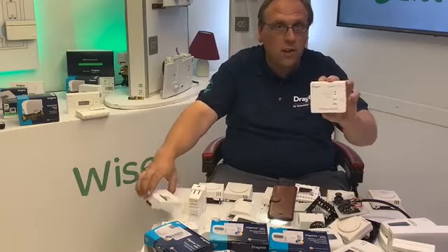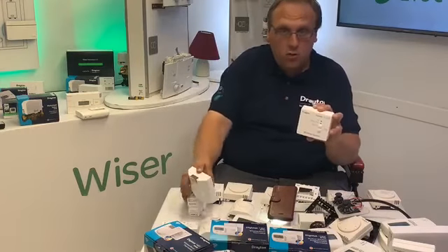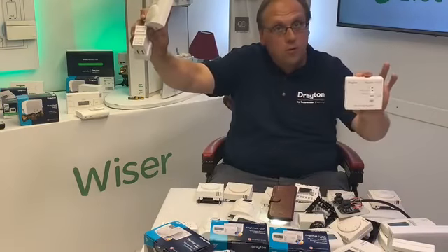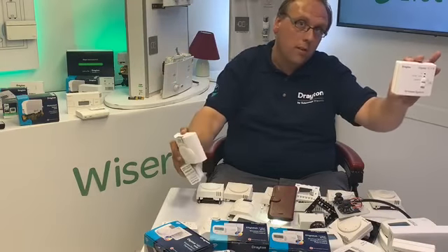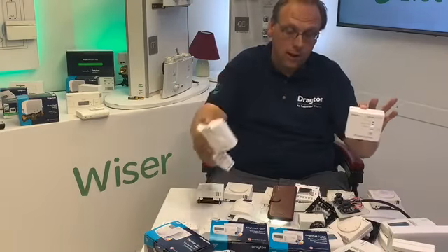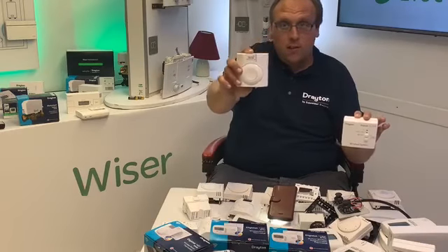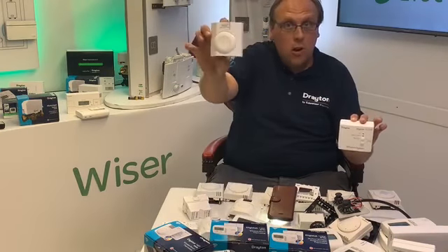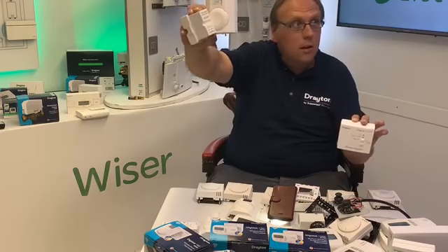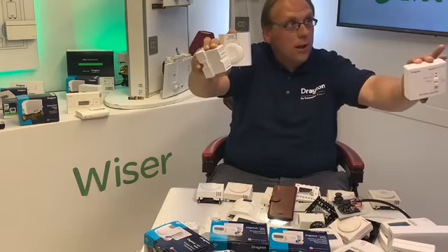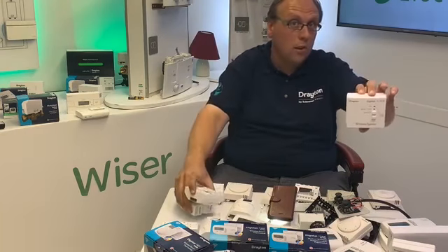So if you've got a cylinder in your loft, say, this is doing the sensing in the loft, your motorised valves may be elsewhere, so rather than running a cable you would put an SCR there, and that's where you get the wireless link. So it's not a wireless cylinder stat in so much as you can walk around the property changing the control, changing the temperature on this. That sits with the cylinder, that goes elsewhere depending on what it is that you're trying to control.